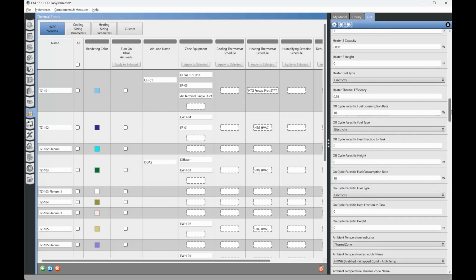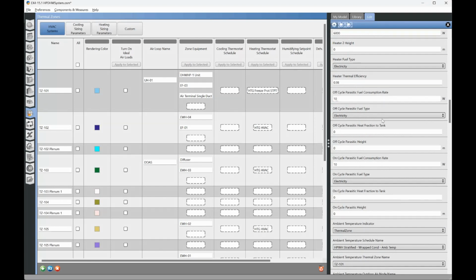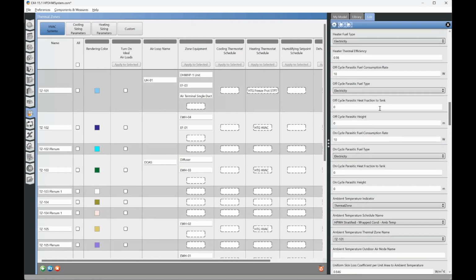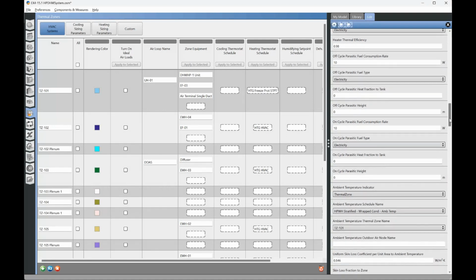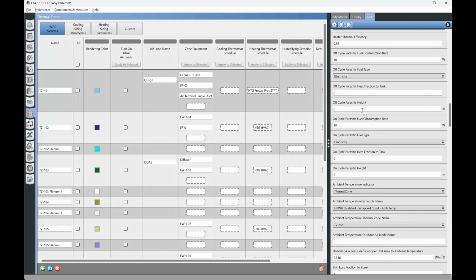Electric energy, thermal efficiency, off-cycle parasitic fuel consumption rate. So when the tank is turned off, is there any lights or beepers or electronics that are operating, electronic displays on the tank that are going to be a parasitic fuel consumption? In this case, the fuel is electricity, so that's what that's going to be.